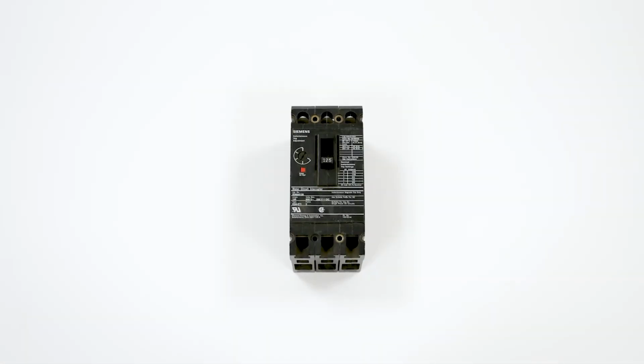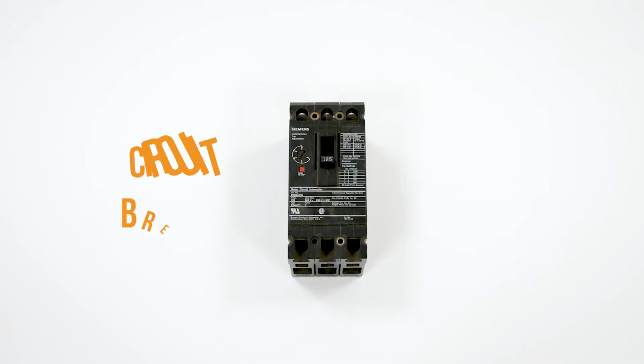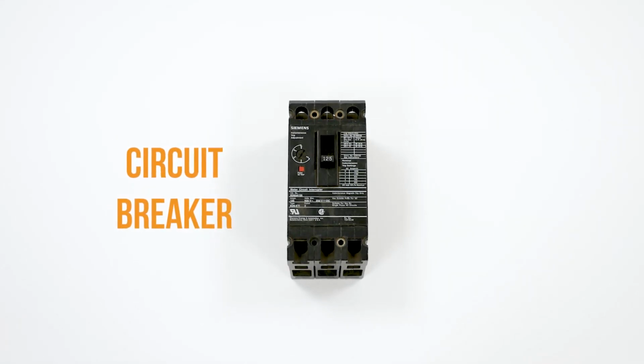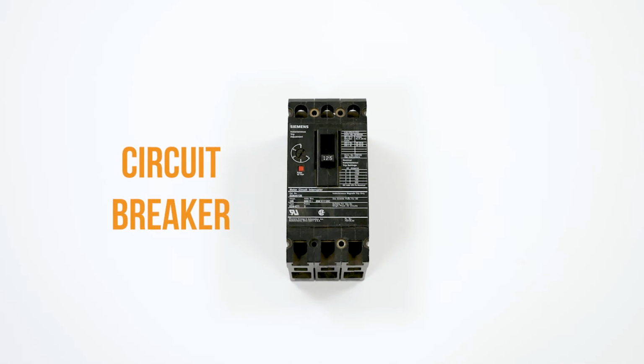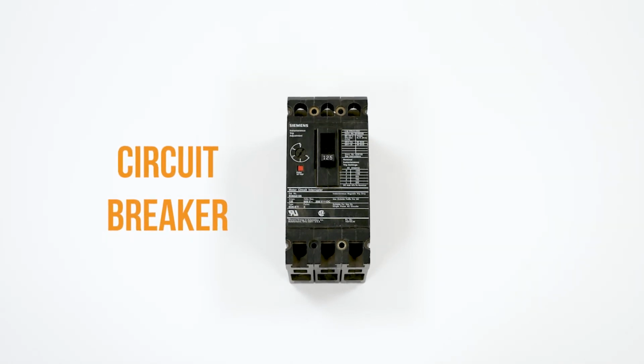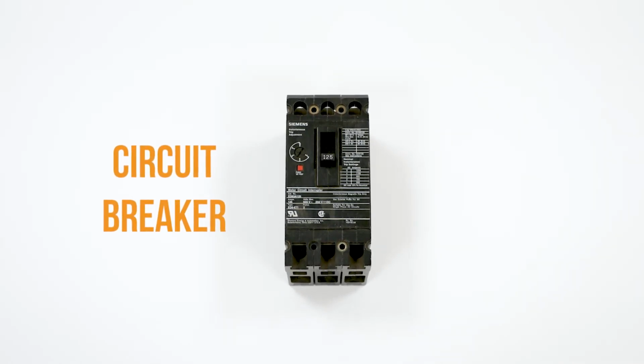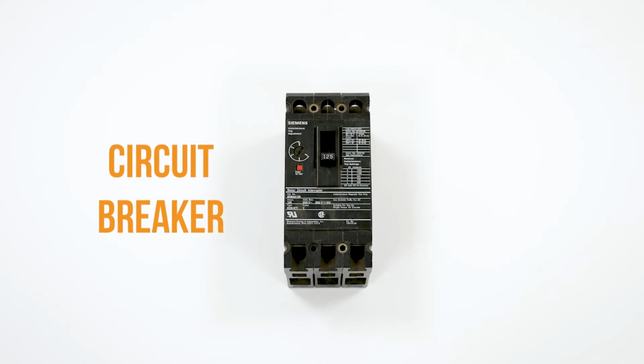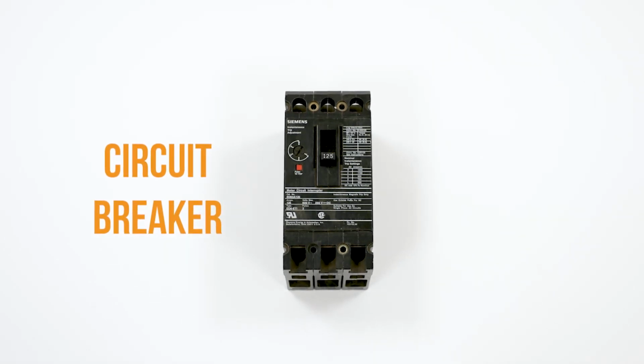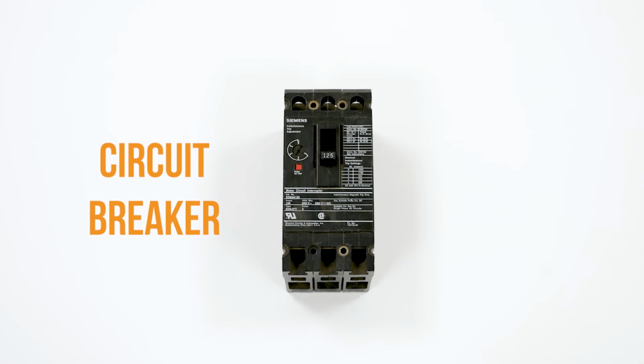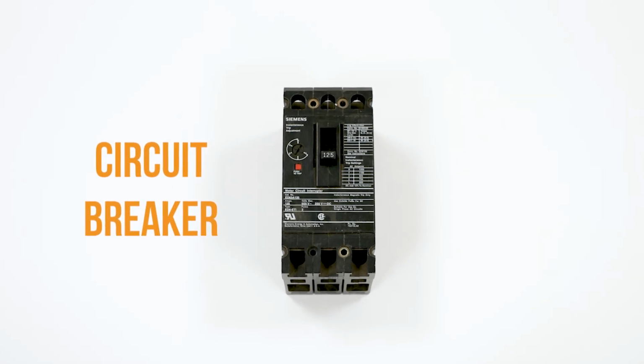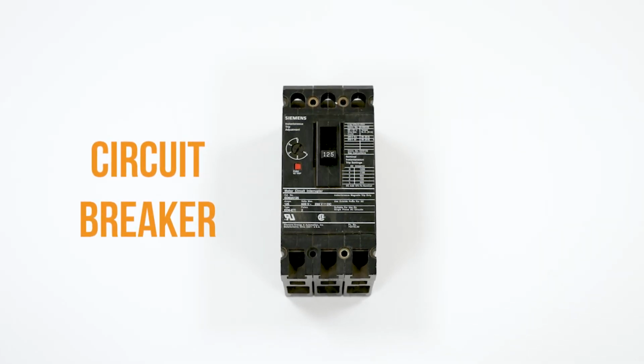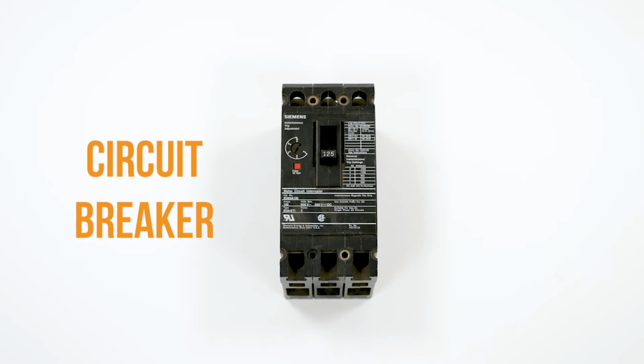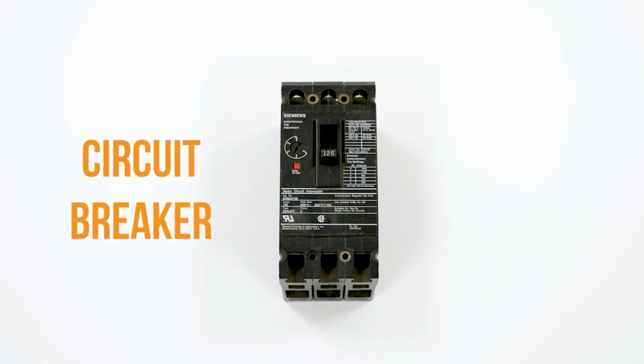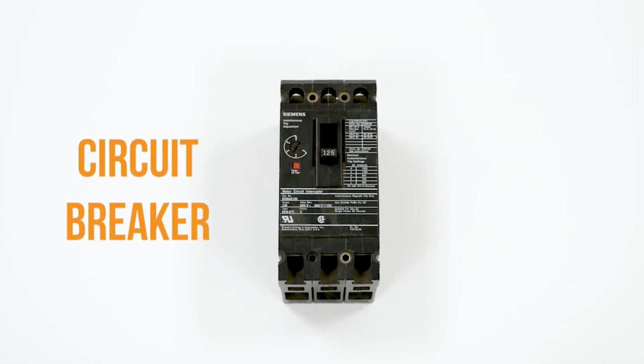The next type of overcurrent protection device that we have is a circuit breaker. These are automatic electrical switches that open or trip when overcurrent is detected. After an overcurrent event, the breaker can be reset, but it's only rated for so many overloads and short circuit trips. Like fuses, these come in a wide variety of sizes, but they have many more accessories like lug kits, extra contacts, and disconnects external to the cabinet that allow you to turn the breaker on or off.